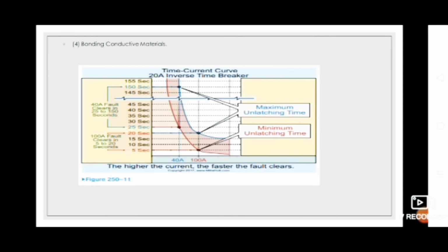Number 4 is bonding conductive material. The time it takes for the overcurrent protection device to open depends on the magnitude of the fault current. A higher fault current value will result in a shorter clearing time for the overcurrent protection device. For example, a 20 ampere overcurrent protection device with an overload of 40 amperes, two times the 20 ampere rating, takes 25 to 150 seconds to open. The same device at 100 amperes, 5 times the 20 ampere rating, opens in 5 to 20 seconds.